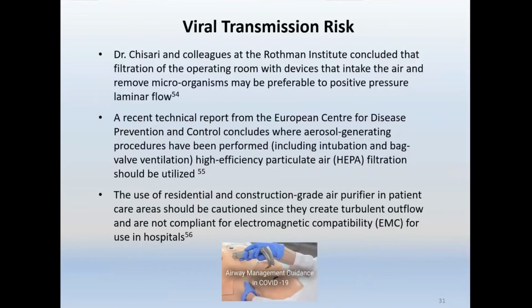A recent technical report from the European CDC concluded that where aerosol-generating procedures have been performed, such as intubation and bag valve ventilation, high efficiency particulate air, or HEPA, filtration should be utilized. We've also seen the use of residential and construction grade air purifiers in patient care areas, but we should be cautioned, because they can create turbulent outflow and are not compliant for electromagnetic compatibility for use in hospitals. Unfortunately, a lot of hospitals said, well, we've used HEPA filters for our construction site, so let's just get a bunch of those, not realizing they're not appropriate for use in healthcare.